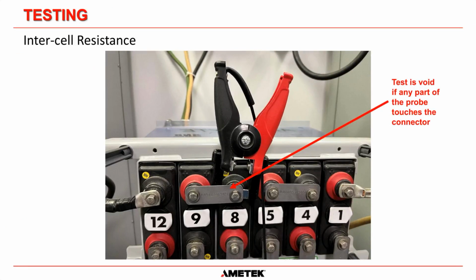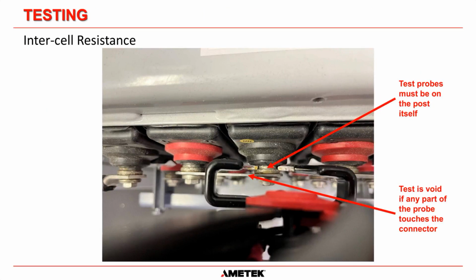Here's another example of a valve regulated lead acid battery. It's one of the stackable versions. Remember, if these probes touched this connection here, then the test is void. There's no point in actually doing the test, none whatsoever. So you have to make sure you get the correct probes for your device. You can see here that the probe is only touching the post. It is not touching the strap connection. So we will be measuring from the post through the connection all the way through to the other side. I didn't show the other probe on here, but it would be connected on that post there, and then it would measure the connection between the strap and the post on the other side.